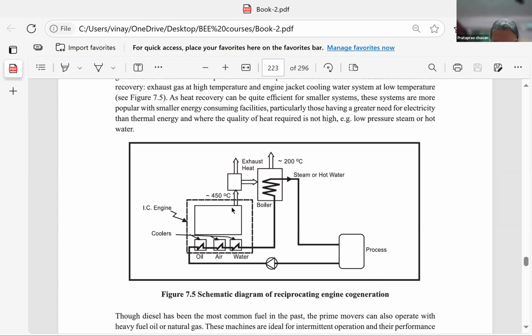So we can extract the heat from these gases, same purpose, the same steam generating coils are there in this boiler. There is no separate fuel for this boiler. Out of 450 degrees temperature, this boiler is absorbing around 250 and gases with 200 degrees centigrade are allowed to go to the atmosphere. Right? The heat is then used for process, cooled down, and goes back to the boiler for heating.